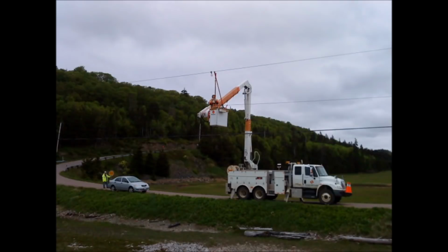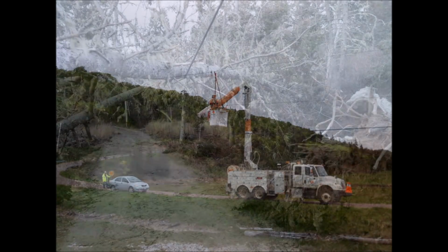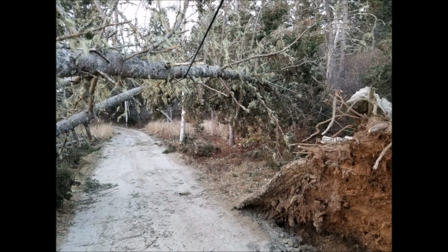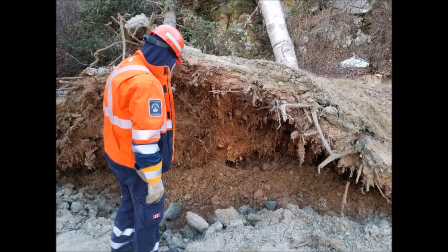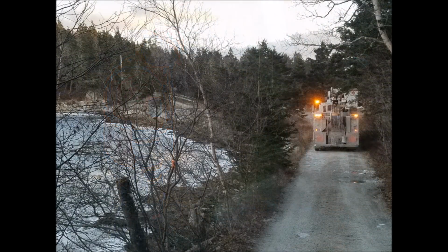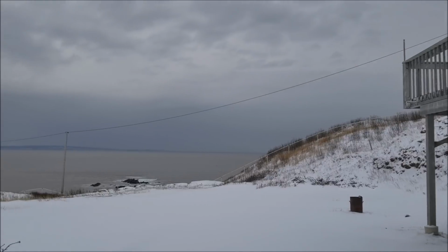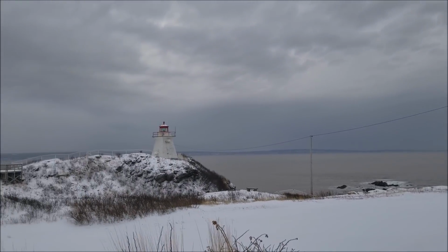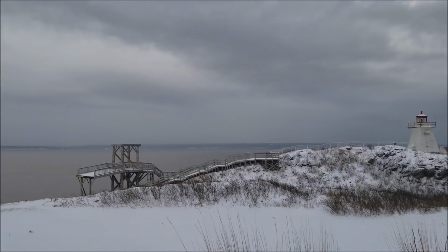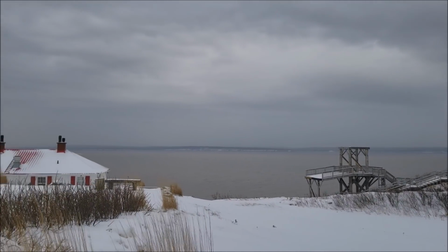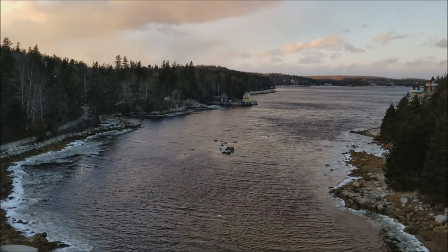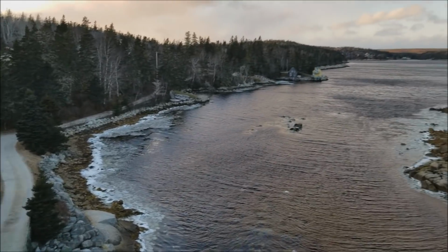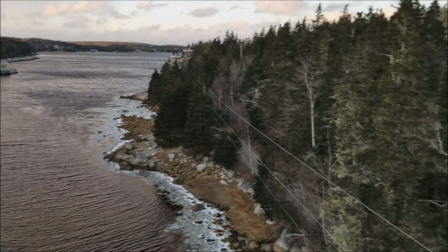In a rural area, one might think an underground line would be efficient at reducing outages caused by high winds and trees, which it would, but again, is just not practical. With no sewage system in place, the cables would have to be buried deep enough to cross below any culverts or ditches. And with miles and miles of empty land, whenever somebody decided they wanted to build a home, in order to supply it with power, we would have to excavate the cable in order to splice in a pad mount transformer at each and every location.